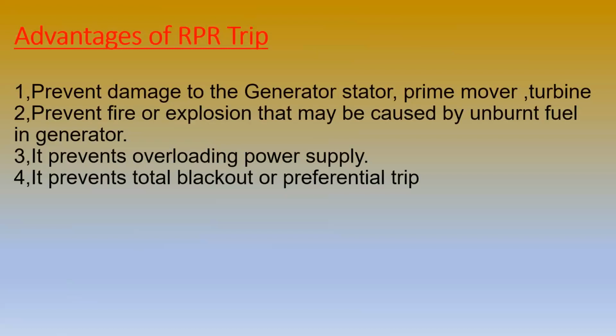So what are the advantages of the reverse power relay trip? When the trip happens, it prevents a blackout in the ship, and it prevents damage to the generator stator, because the stator starts to take power and acts like a motor. So the prime mover, turbines, and these things are protected from damage. It prevents fire or explosion that may be caused by unburnt fuel in the generator. It prevents overloading the power supply. It prevents total blackout or a preferential trip. So these are the advantages of the reverse power relay trip: preventing damage to the generator and preventing damage to the prime mover and turbine.